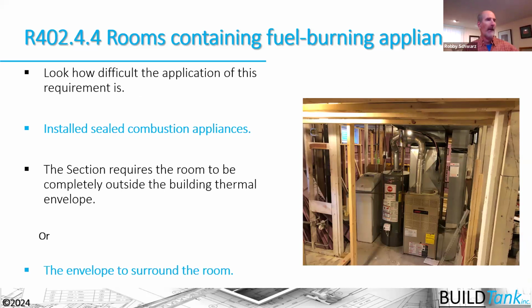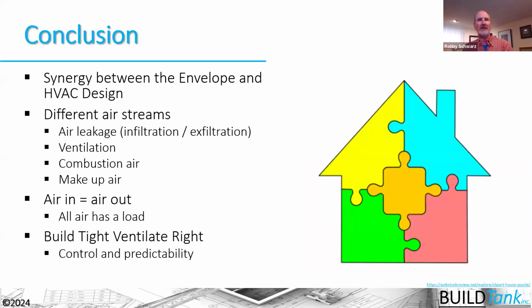Okay, so we have gotten to the conclusion of our assignment today, thinking about infiltration, ventilation, and HVAC loads through the Manual J here. So we really need to understand that synergy between the building thermal envelope and the HVAC design. The basic definition of synergy is two or more things coming together to be able to achieve something that we couldn't achieve before or individually. So the envelope and the HVAC design, or the envelope and the mechanical equipment together, right sized and executed well, are going to give us that well-performing house there. We can't do it separately there.